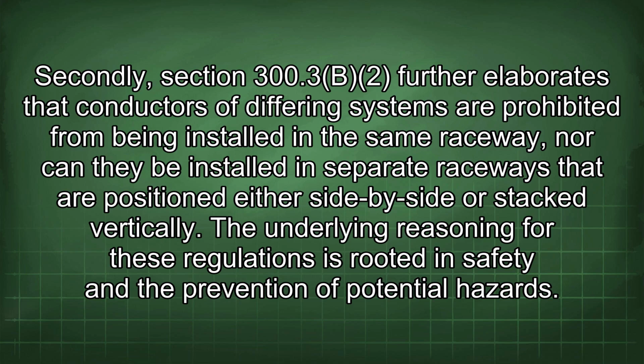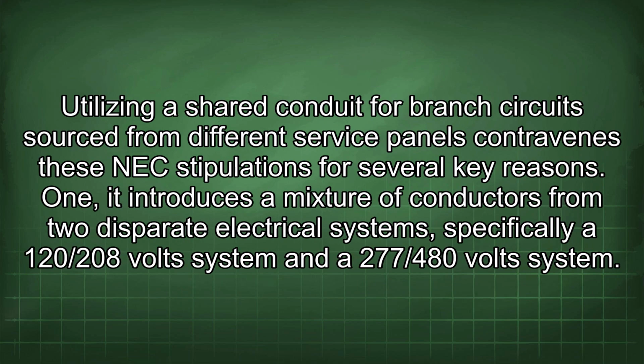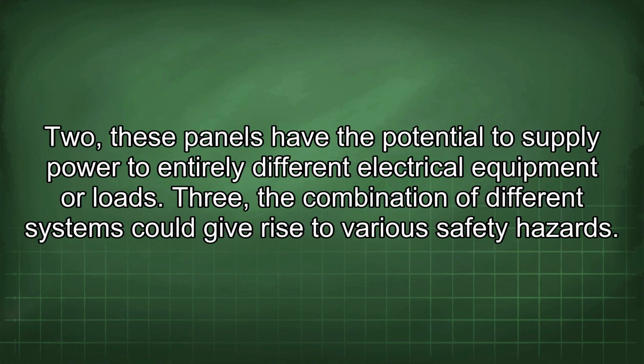The underlying reasoning for these regulations is rooted in safety and the prevention of potential hazards. Utilizing a shared conduit for branch circuits sourced from different service panels contravenes these NEC stipulations for several key reasons. 1. It introduces a mixture of conductors from two disparate electrical systems, specifically a 120/208 volt system and a 277/480 volt system. 2. These panels have the potential to supply power to entirely different electrical equipment or loads. 3. The combination of different systems could give rise to various safety hazards.